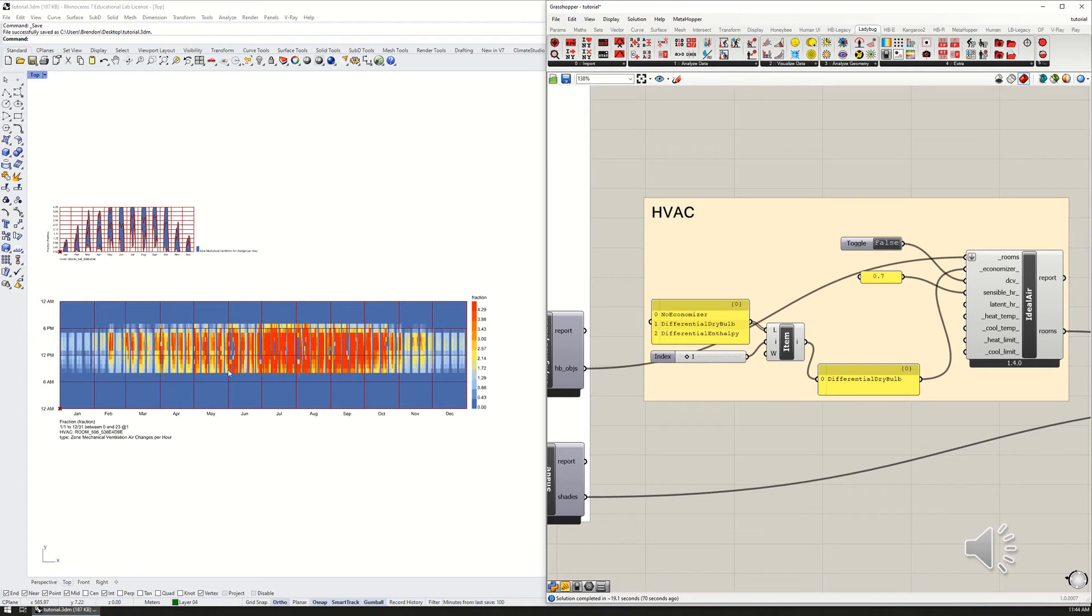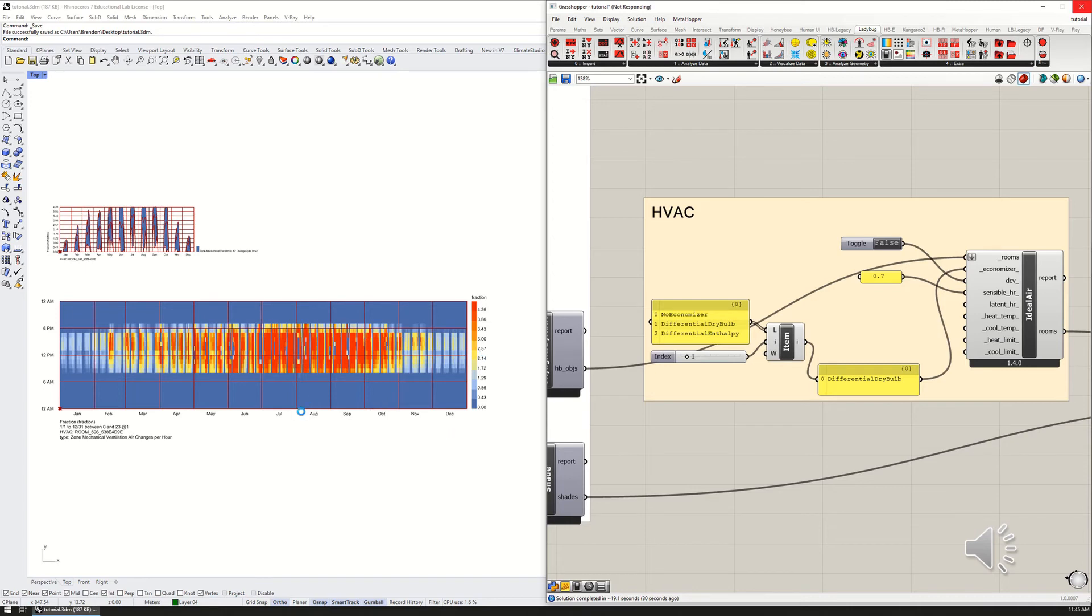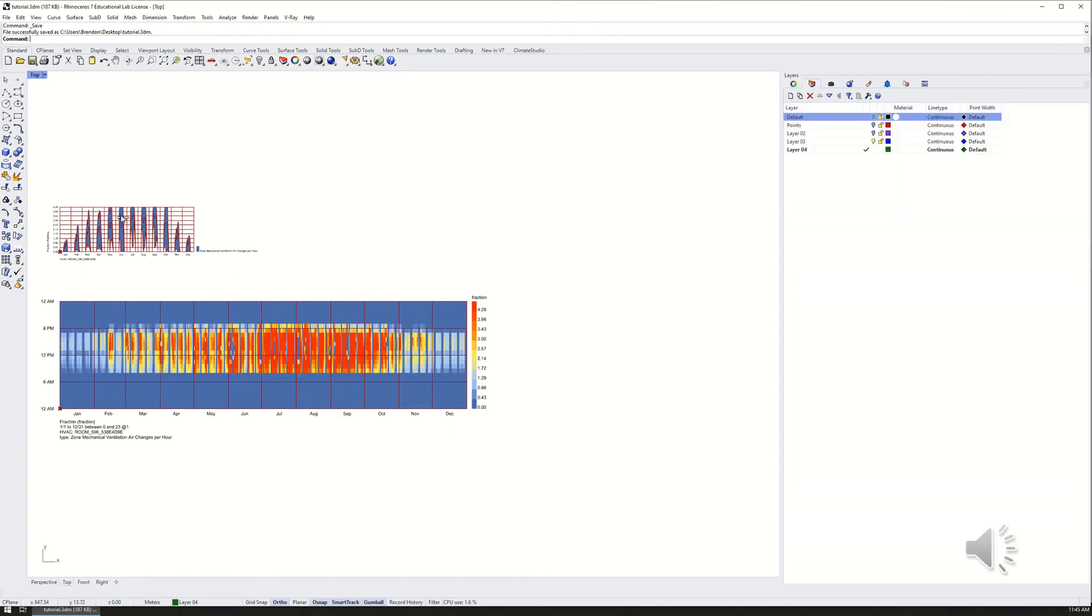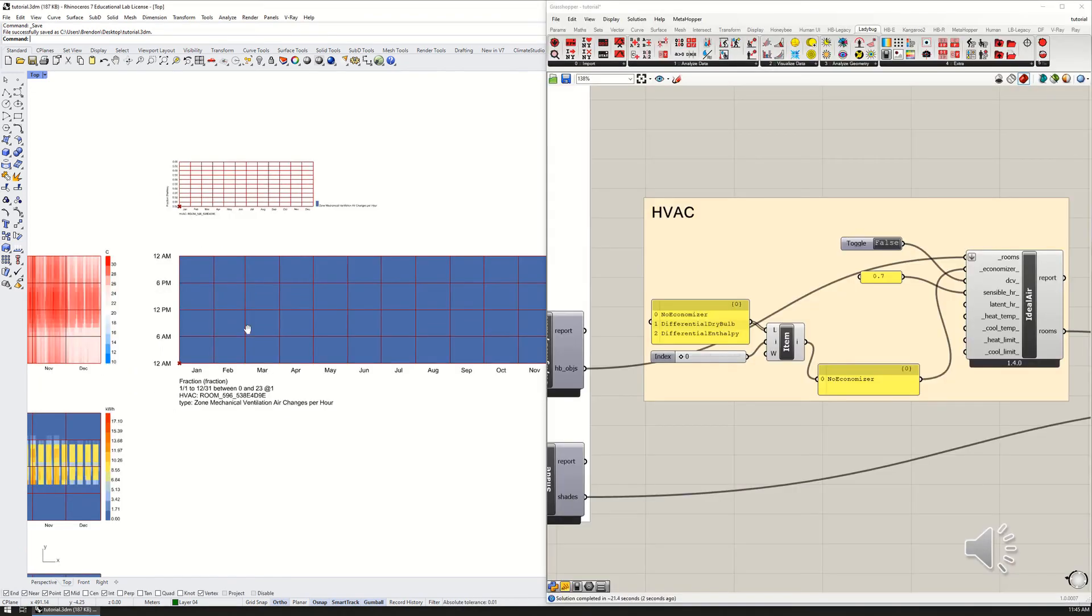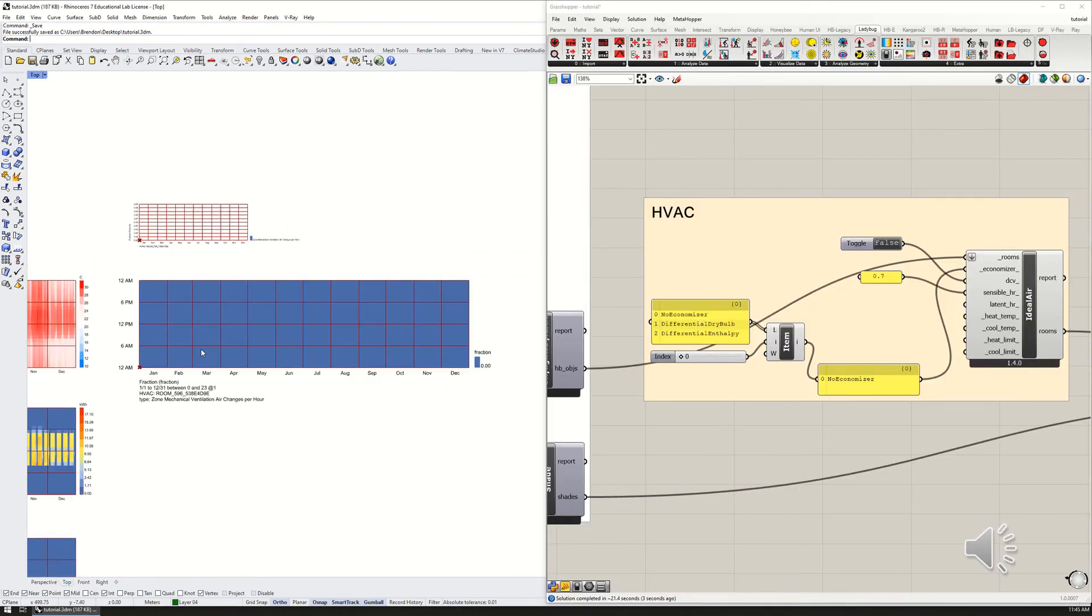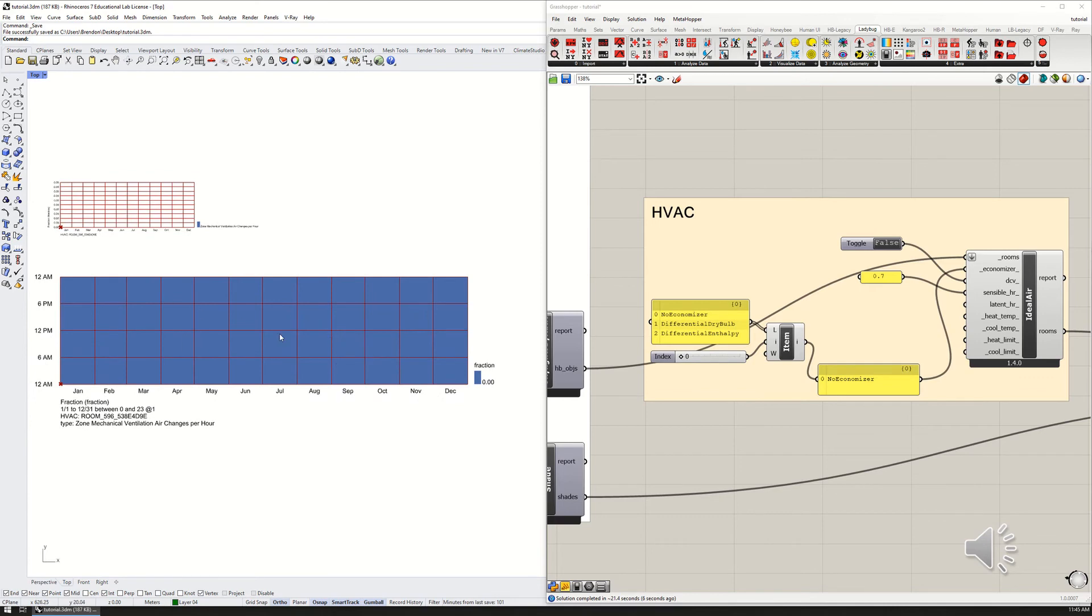That's what you're seeing here—we're getting fresh air, cooler outdoor air coming in to cool down the zone. If we change this from differential dry bulb economizer to no economizer, turn off the economizer, we should see that airflow rate go to zero. It's running right now. Let's see what happens here. This should turn blue and this graph should go to zero.